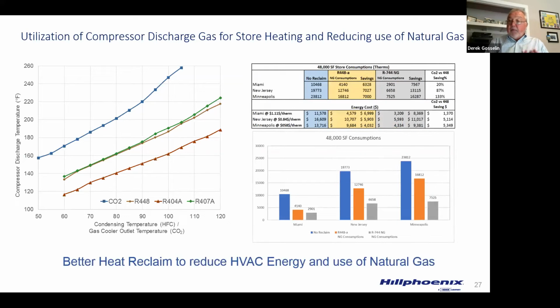An example of this will vary, as I said earlier, everything needs to be compared to your baseline and your regional area, which Andre talked about. If you use heat and better utilize it by direct feeding into your HVAC system, it gives you the ability to reduce HVAC energy use and also reduce natural gas use. How many therms can I say, how much less natural gas do I have to burn because I'm better utilizing heat reclaim? I think that's a big push going forward when we look at what impacts our decision-making process and how we make the best decision.